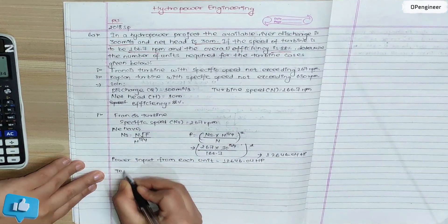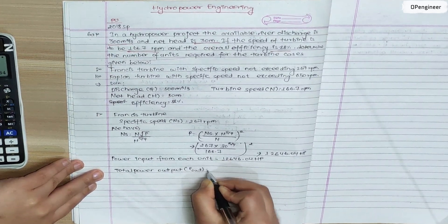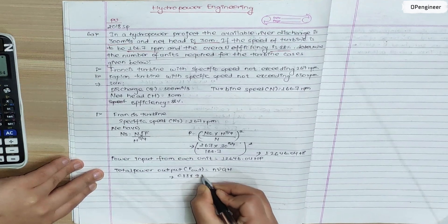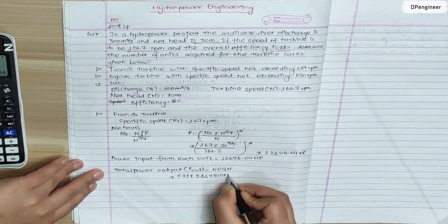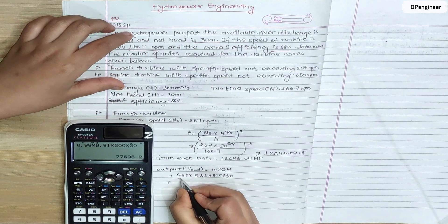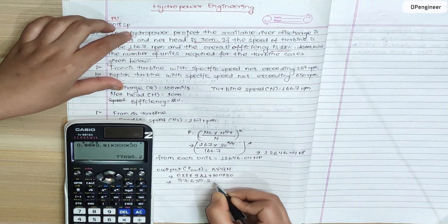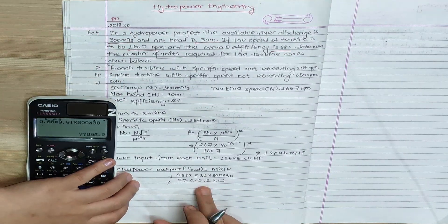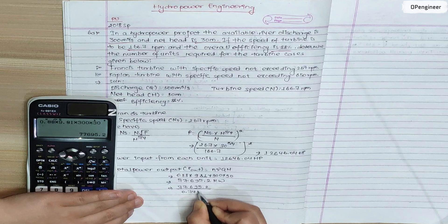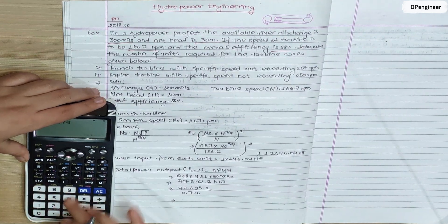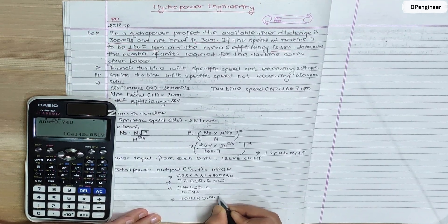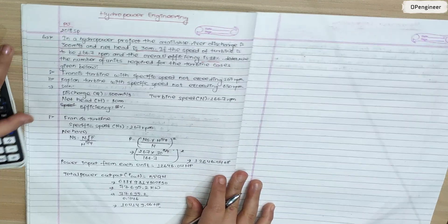Now we need to calculate the total power output. The formula is P output = efficiency times gamma times Q times H. So 0.88 times 9.81 times 300 times 30 equals 77695.2 kilowatts. Converting to horsepower: 77695.2 divided by 0.746 equals 104149.06 horsepower.